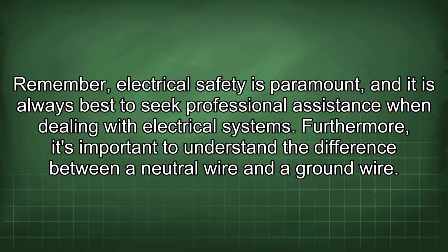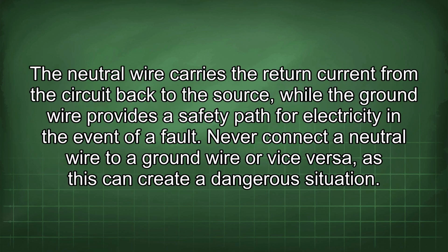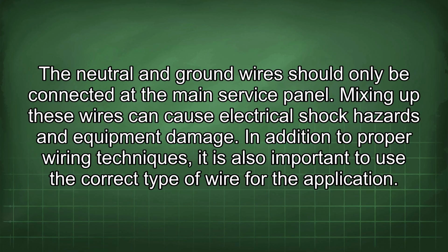Furthermore, it's important to understand the difference between a neutral wire and a ground wire. The neutral wire carries the return current from the circuit back to the source, while the ground wire provides a safety path for electricity in the event of a fault. Never connect a neutral wire to a ground wire or vice versa, as this can create a dangerous situation. The neutral and ground wires should only be connected at the main service panel. Mixing up these wires can cause electrical shock hazards and equipment damage.